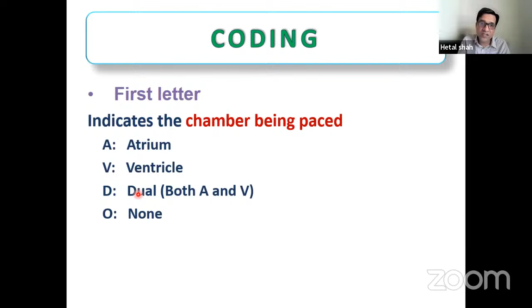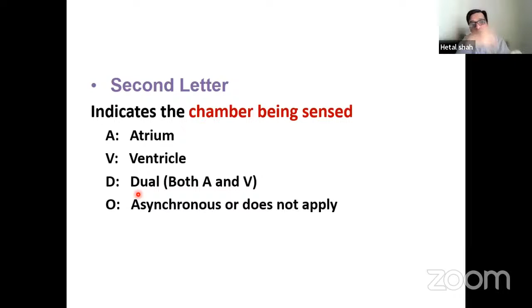The second letter indicates the chamber being sensed. Again, it's A, V, D, or O. There is a signal going to the machine, that is, the signal is sensed by the pacemaker, and according to that signal the pacemaker paces the first letter chamber, right? And the third letter is the generator's response. Whatever signal has come to the machine from the second letter chamber, what the generator has to do with that signal.